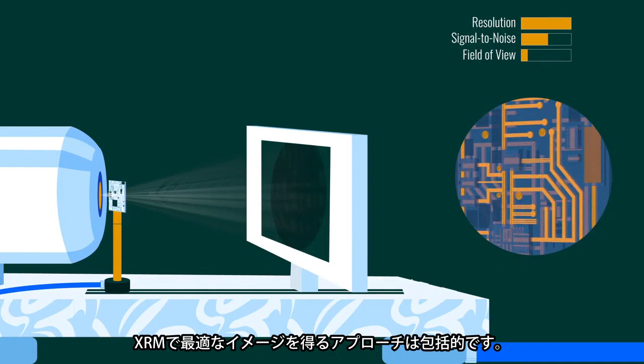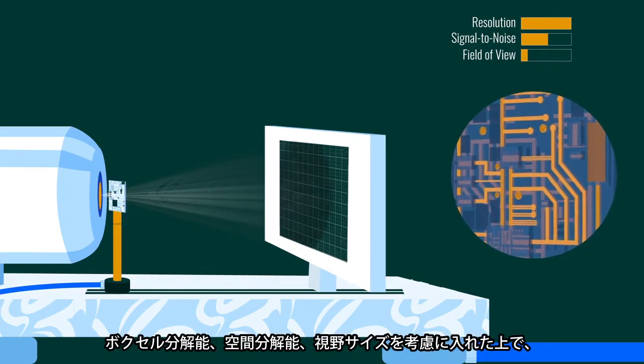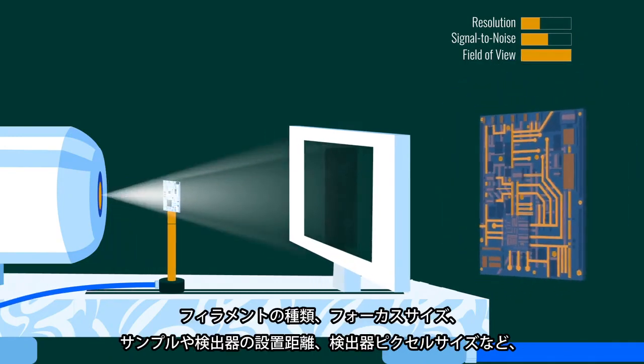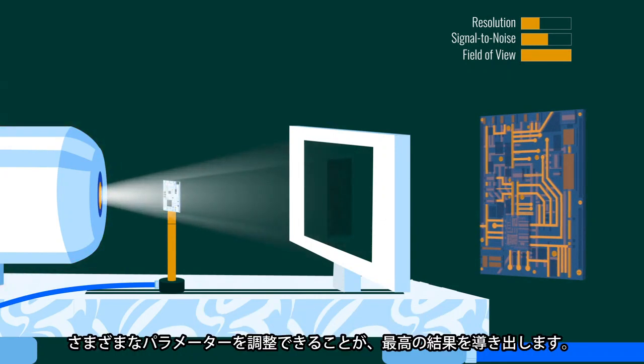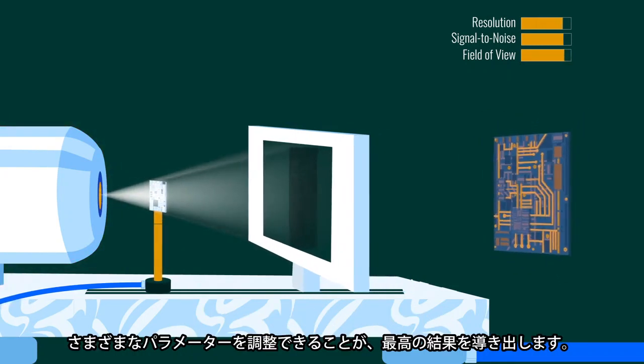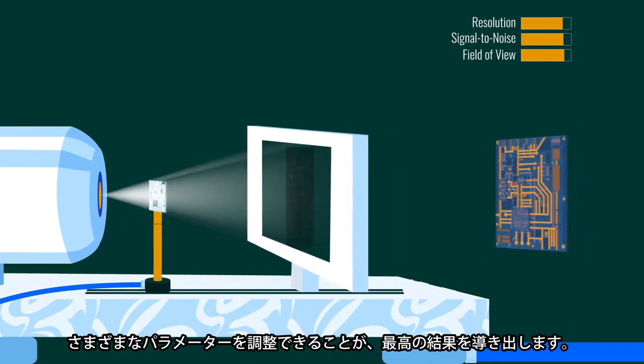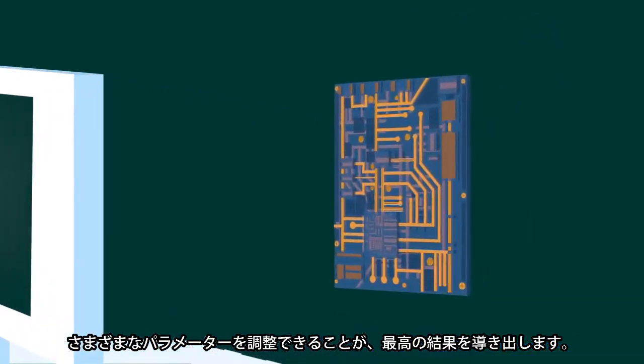The best approach to XRM is holistic, taking into account the voxel resolution, spatial resolution, and field of view. Having access to a multitude of tunable parameters including filament type, focal spot size, sample and detector distances, and detector pixel size are all important in achieving the best results.